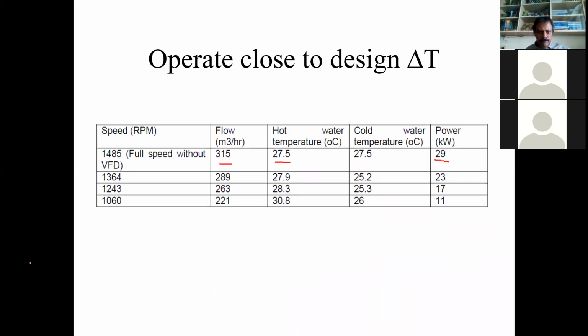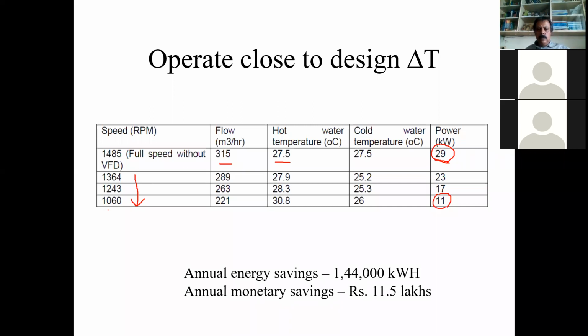As we reduce the speed, we keep on reducing the speed till again you optimize on the power consumption for the compressor. The discharge pressure of the compressor is to be monitored here. Keep on reducing the speed, and the flow rate keeps on coming down. So this is the power consumption at the most optimum speed of the condenser water pump. Earlier at full speed it is drawing 29 kilowatt. Now it is drawing only 11 kilowatt. So this is again, when we are studying pumps, many times cooling water pumps have to be studied in conjunction with the process as well as the cooling tower performance.